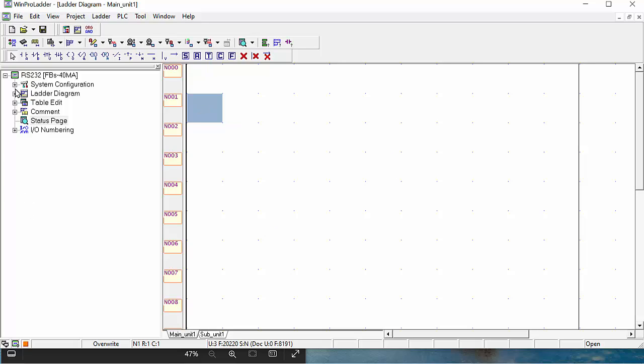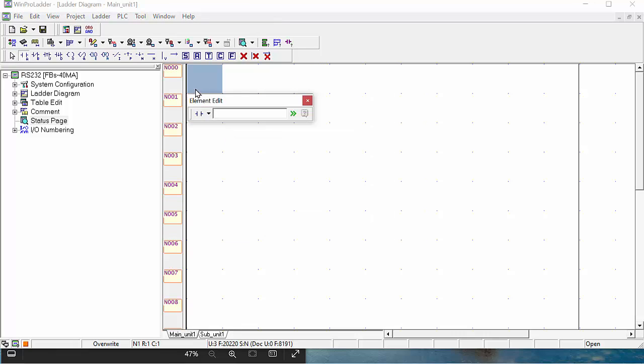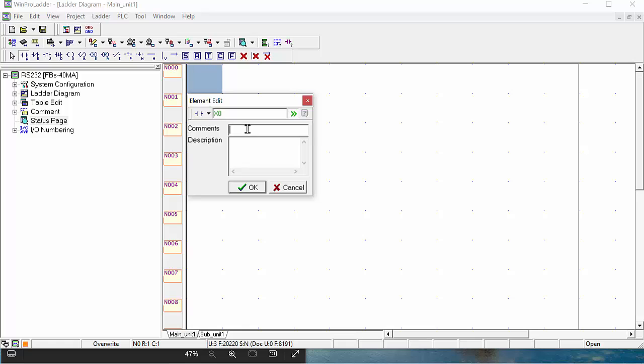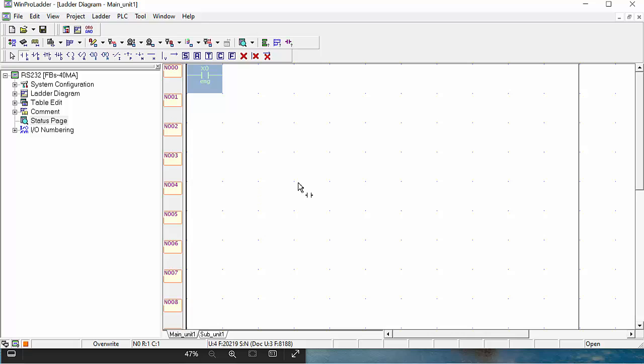First, I will take a small bit for on control, like your push button, selector switch, emergency button, or whatever button you like to make in your hardware. That is the same as an NO contact. Here you can give the address of this NO contact. In FATEK PLC, the input addresses are defined as X0 to X255. We will use X0, and you can give comments here. For example, I will give here EMG for emergency button, and description for where it's placed, then click OK.